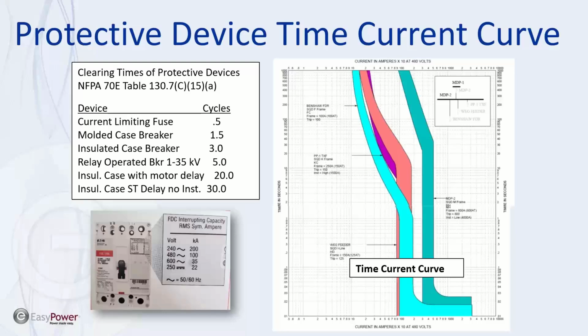So the point is, if a maintenance person is going to put in a sub panel for a new test area or something, or a disconnect switch, so they've got a disconnect switch like this, this breaker goes in the disconnect switch. If they've got a disconnect switch that's rated for 10,000 amps, and they're putting it into an industrial facility that's 65,000 amps available, that's going to be a problem. It's going to blow up instead of operating the way it's supposed to.